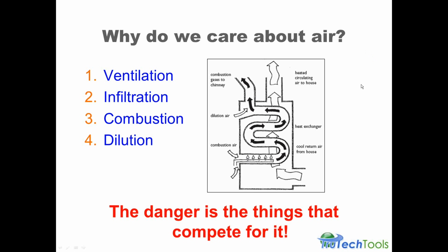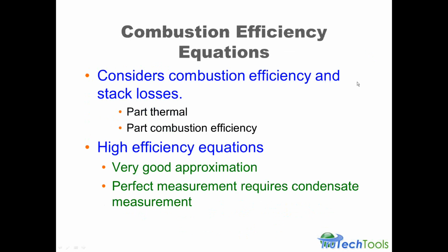So we have competition for air. Now let's move to what are combustion efficiency equations. The equations themselves are really a hybrid of thermal and combustion efficiency. The thermal part of it tells you the efficiency of heat transfer over your heat exchanger, because it's measuring the flue gas temperature, which is the temperature after it's passed over the heat exchanger and the heat should be extracted. And it also measures the combustion efficiency by measuring the oxygen and the CO. Primarily it's the oxygen, to see how completely combustion has happened and how much excess air is available. So those two numbers are put together by the combustion analyzer manufacturers to come up with a hybrid or a composite number that's called the combustion efficiency, the steady state efficiency.